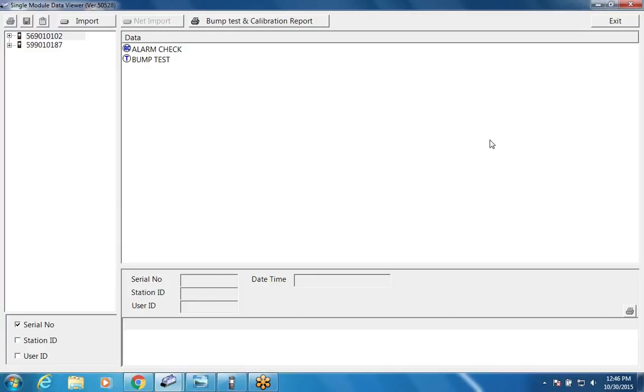So this is the main screen you're going to see when you turn the unit on. So like our other docking stations, you can do a bump test, you can do a calibration. The alarm check is something that's new, and that's also something that we were asked for. If you're doing a calibration or a bump test, you can have it also do an alarm check, which will basically check to make sure that the buzzer and the vibrator and the LEDs are working. And that's something that some of our competitors had and something we were asked for.